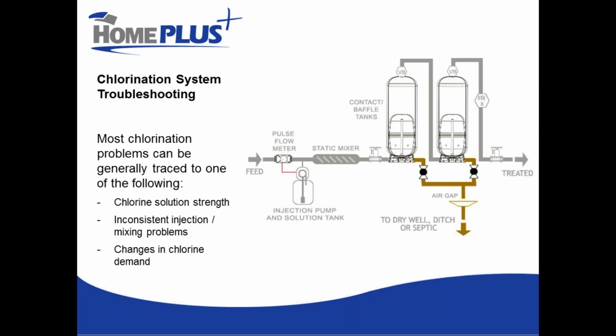All right. So chlorination. I've got a picture here of a typical chlorination system. Obviously, there's variability in how they work and the specific pieces of equipment, but generally we have an injection pump that draws chlorine solution out of a tank, might be controlled by a flow meter so that we can inject the chlorine in an amount proportional to the water flow. So more chlorine when flow rate's higher, less chlorine when flow rate's lower.